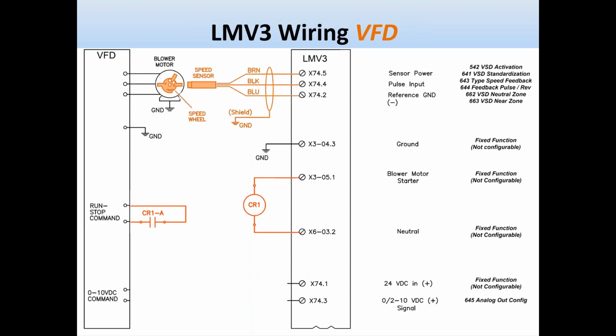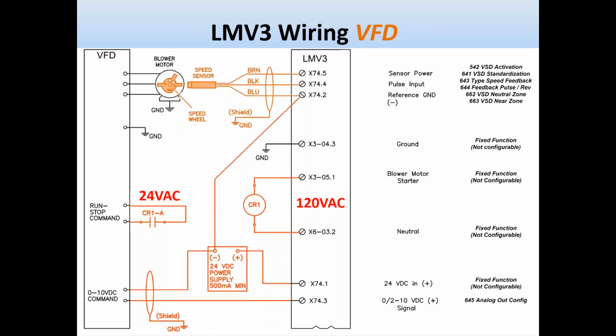Next, we will need a relay. The LMV3 does 120 volt output. The VFD typically takes a 24 volt AC or DC input. So the 120 volt relay would dry out that contact and you would take 24 volts, in this case usually from the VFD, 24 volts DC, and take it through the CR1 and back, and this would start and stop the variable frequency drive when the LMV3 energizes and de-energizes the 120 volt terminals. Additionally, you'll have to add a power supply, 24 volt DC power supply. This would provide power for the speed sensor, and it also provides power to the LMV3 so that the 0 to 10 volt modulation signal can go to the VFD.